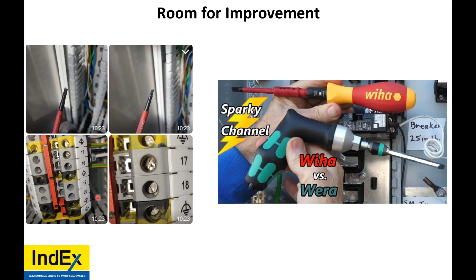What else do we see in the industry? We see manufacturers ship devices with plugs, blanking elements, and glands without any EX markings on them. Is this acceptable? Well, per the general requirements, even for very small pieces of EX equipment or components where there's no practical space for marking, I'd digress and say there is space here. Where there's no practical space, a marking intended to be linked to the EX equipment or component is permitted.